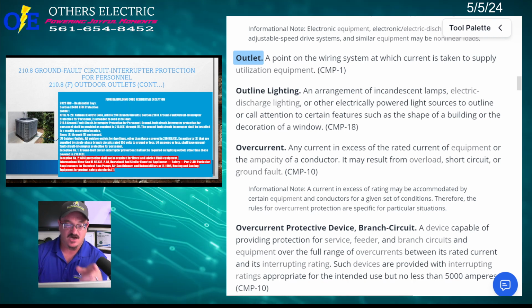Okay, so let's talk about these condensing units. Now, how do I want to go about this? So you remember when I told you in the beginning that the Florida Building Code dictates how and what we get for our codes? Well, there's an exception in the Florida Building Code under Chapter 27 or 34 that pertains to GFCI protection for condensing units. And I want to read it right here. Okay? So the Florida Building Code amended it, basically saying we're going to take everything out of the National Electrical Code 2020 and make it our code except these things. And that exception is number 2. I'm just going to read this one here. Exception number 2: GFCI protection shall not be required for listed and labeled HVAC equipment.